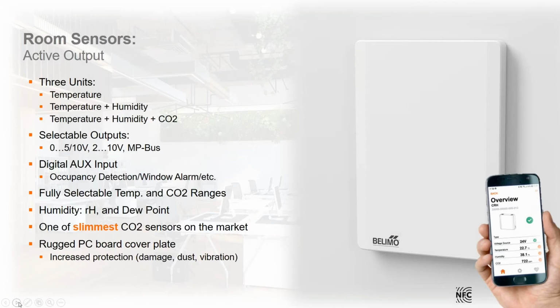These sensors also incorporate a digital auxiliary input. So these are used differently based on different applications, but one of the biggest applications that we see really is occupancy detection. So if you have an occupancy detector wired into the sensor itself, you could have somebody walk into the room, your occupancy sensor will send a signal to the room sensor to wake it up, which will also speak to the BMS system as well. These are also used a lot of times with window alarms and stuff like that. If a window's open, it'll send a signal to the BMS system for you.